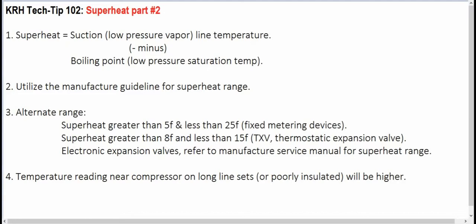In this video we're going to talk more about superheat and we're going to keep it short and sweet. Superheat is the suction low pressure vapor line temperature minus the boiling point low pressure saturation temperature. We had talked about this in the last video that we would prefer to utilize the temperature that a refrigerant is boiling and or condensing at versus looking at the pressure.